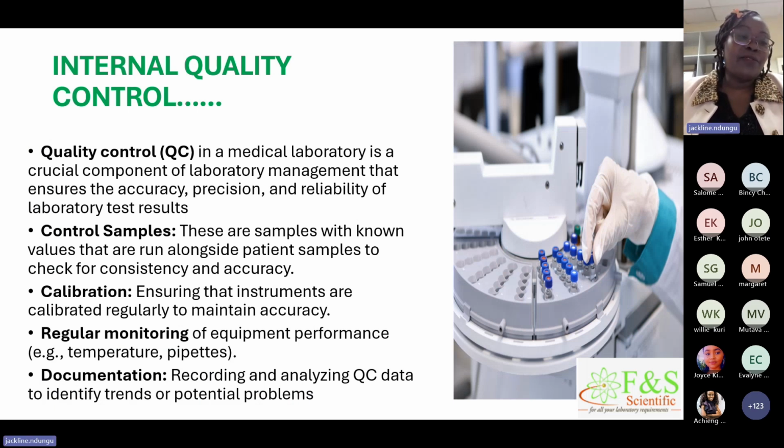As we continue, quality control is a crucial component. Once you ensure the issue of accuracy and precision, when you run your IQC, you're actually trying to continuously verify that whatever you did as a validation or verification before is still there. That is why, in terms of long-term precision, which I have not mentioned, let me mention it right now: once you do your IQC, you will check your monthly QC data and look at the CV that is coming out. You'll know if this equipment is precise. That will really help you check your precision, your accuracy, and the reliability of your results.